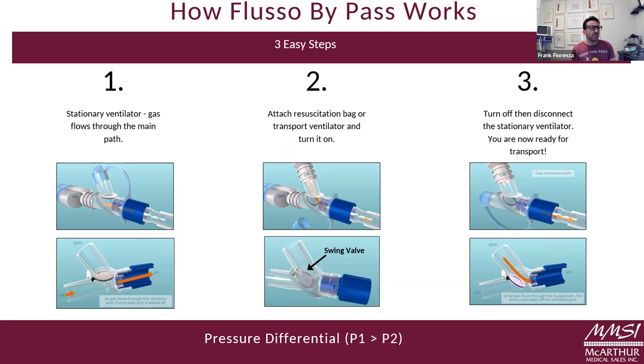As soon as you do that, the pressure at the bypass port will be greater than the pressure at the ventilator port. And that swing valve is lazy and will just jump over instantly and close off the ventilator port. So then you would cap the port you're not using and you can go about your merry way on transport or change whatever component you were looking to change.